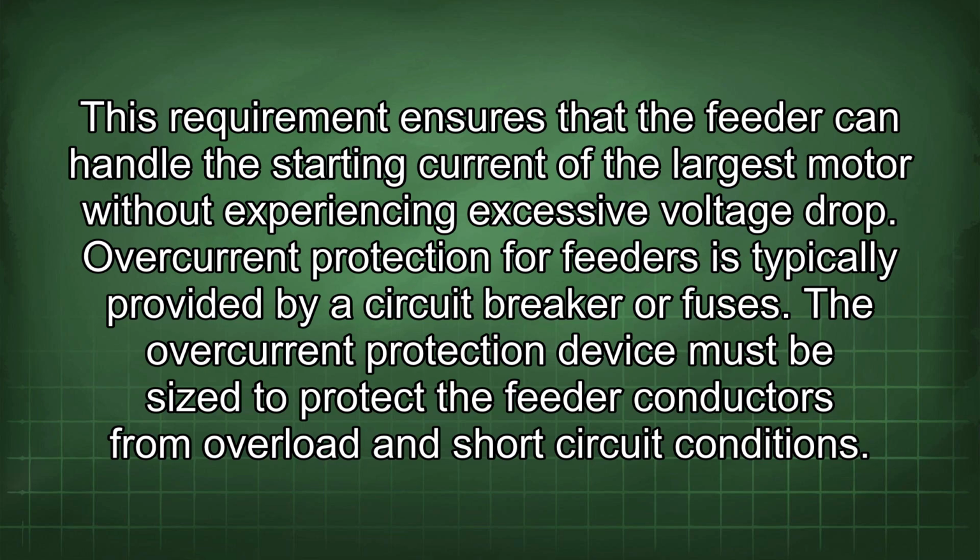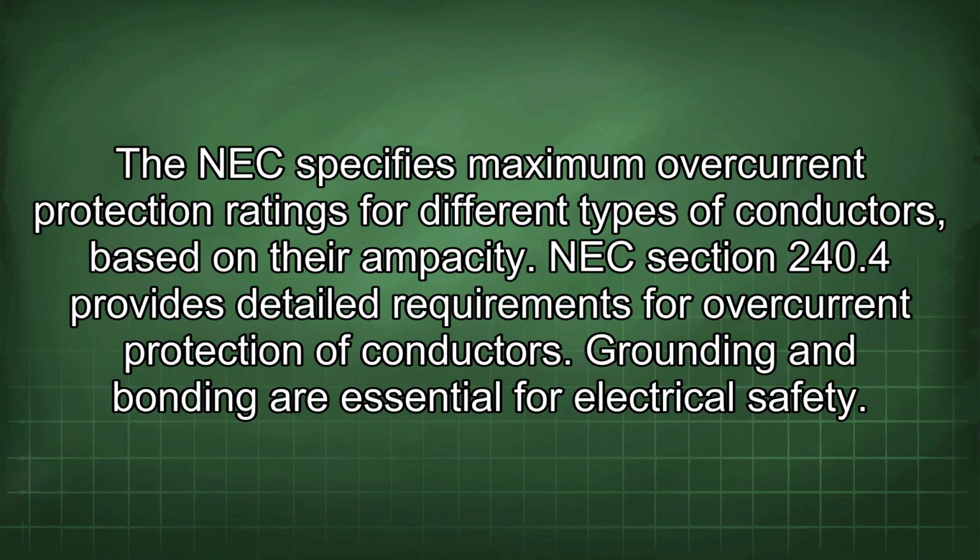The overcurrent protection device must be sized to protect the feeder conductors from overload and short-circuit conditions. The NEC specifies maximum overcurrent protection ratings for different types of conductors based on their ampacity. NEC Section 240.4 provides detailed requirements for overcurrent protection of conductors.